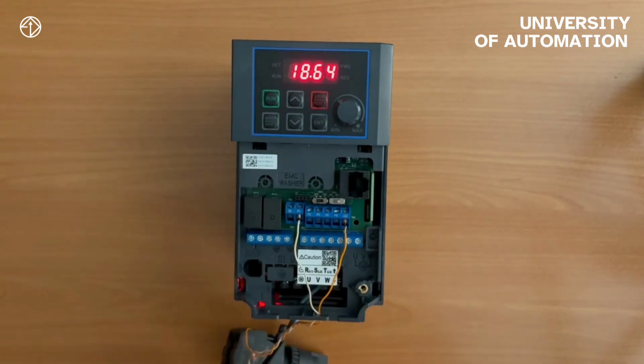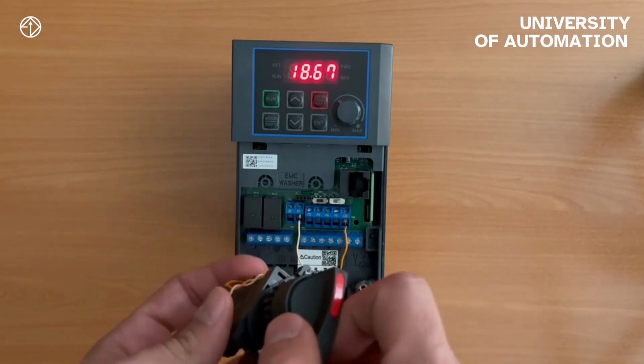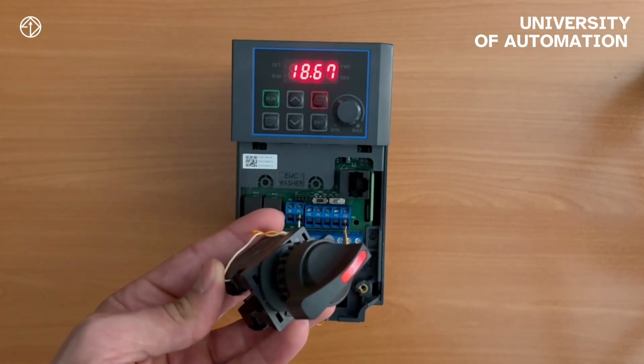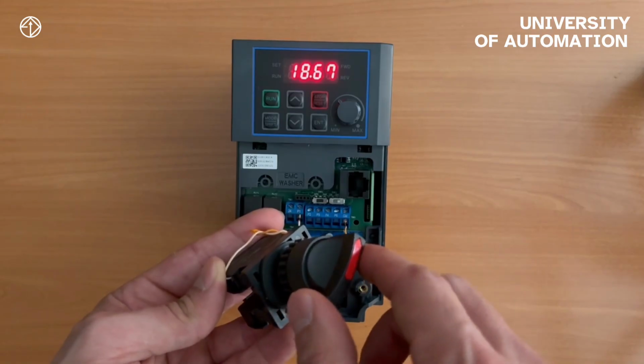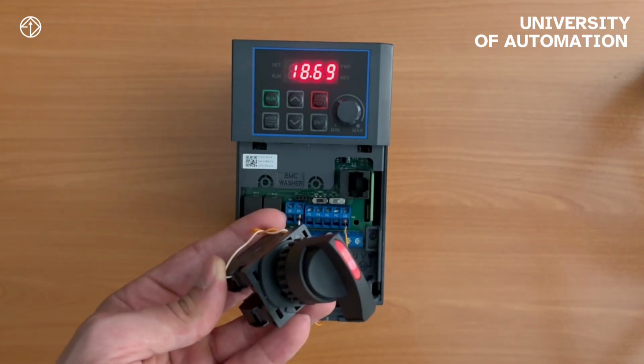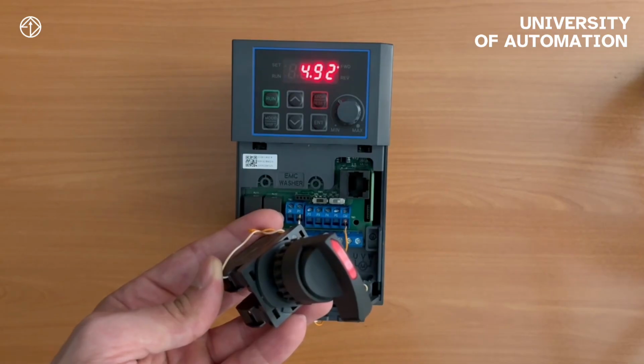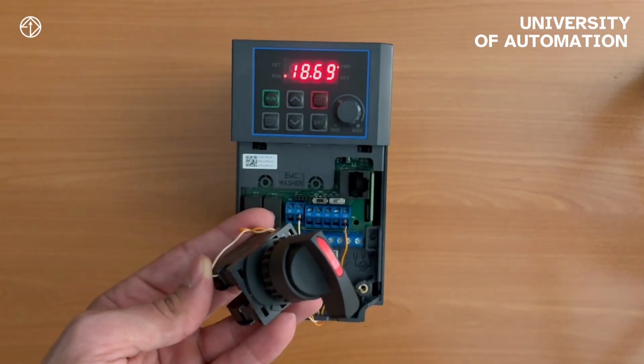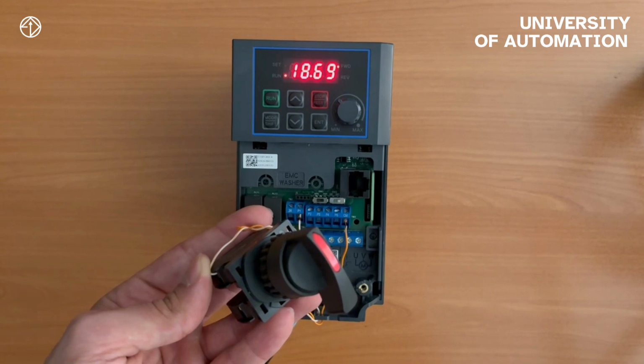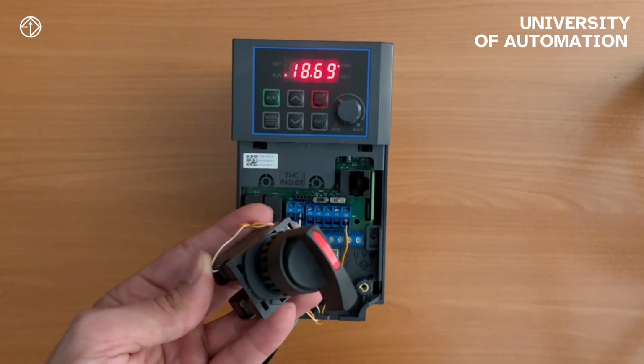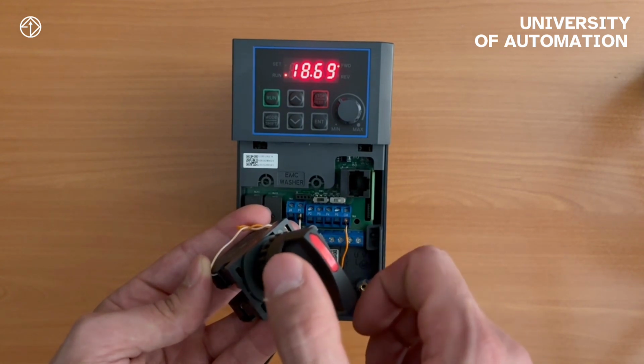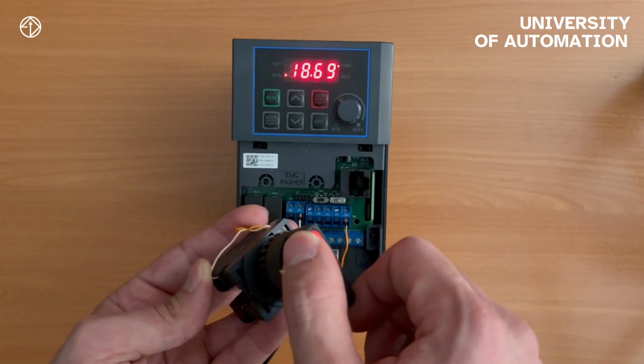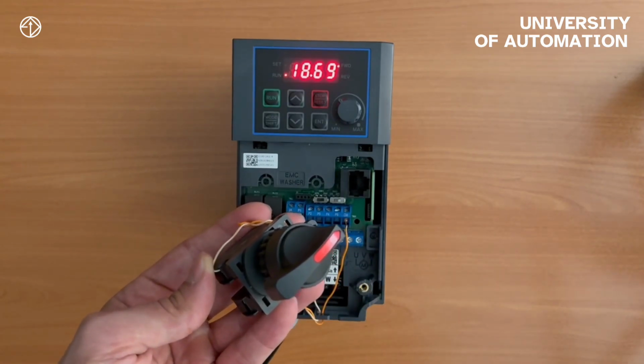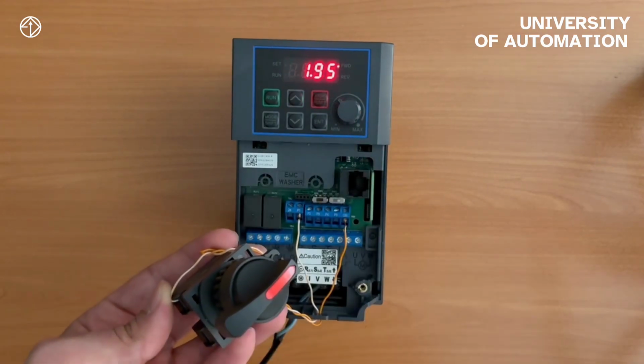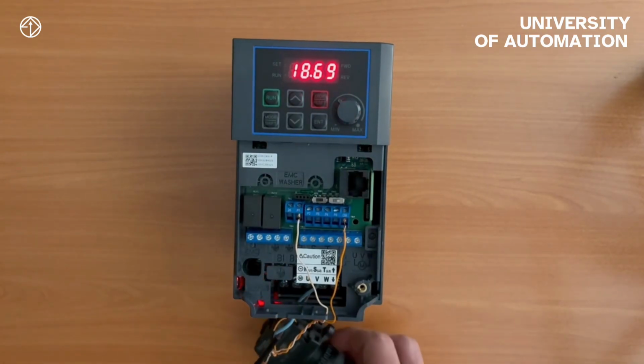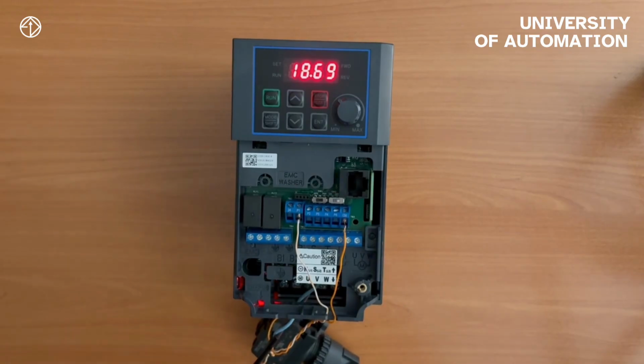All right, now I have activated digital input P1. Now, if I activate digital input P1, the inverter should start after 5 seconds. I have activated it. You can see that after 5 seconds, my inverter started because I had set the delay time for its activation. Now, if I deactivate my digital input, after 3 seconds, this event should happen. The digital input has been deactivated. After 3 seconds, you can see that my inverter stopped. So this is the delay time, or in other words, setting a filter for the digital inputs.